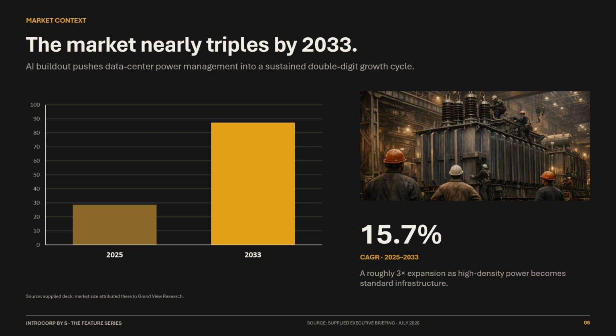The important point is not only the headline growth. High-density power is becoming standard infrastructure, which means demand reaches beyond a single product cycle and into transformers, switchgear, UPS systems, distribution, and rack-level power electronics.